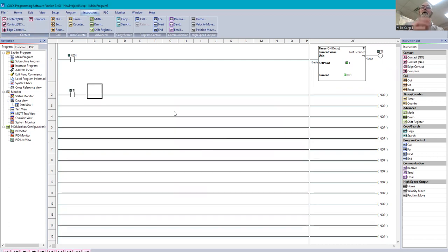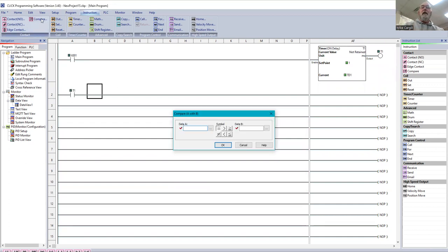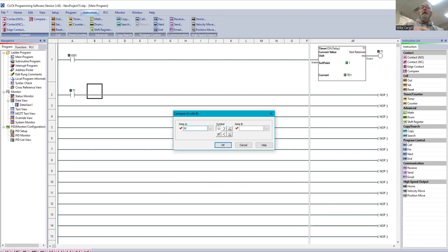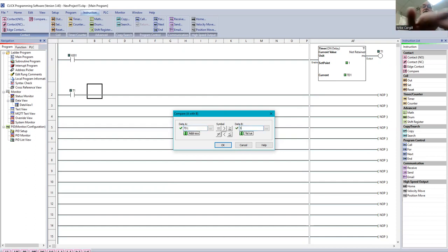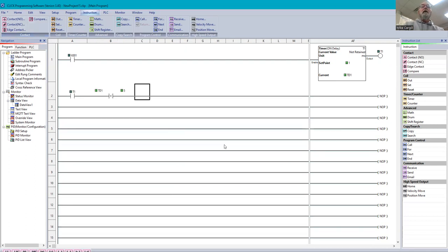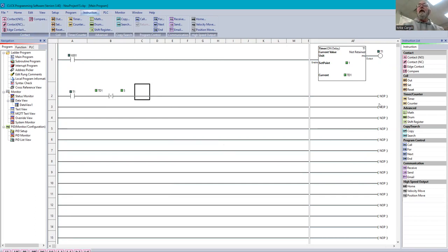So now we're going to put an open contact. We're going to put T1. That's our timer. And now we're going to compare. We're going to put a compare in, which we've talked about in the past. We're going to use TD. Now, TD is the time that's actually running on the clock on T1. So we're going to use T1 and we're going to say if it's less than five seconds, we want the time less than five seconds.